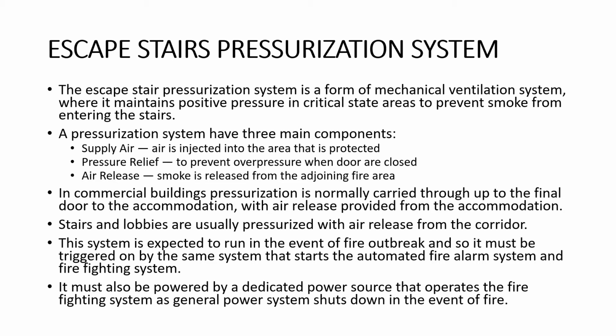For escape stairs pressurization system, the escape stair pressurization system is a form of mechanical ventilation system where it maintains positive pressure in critical stair areas to prevent smoke from entering the stair. A pressurization system has three main components. The first one is supply air, second is pressure relief, and the third one is air release. For supply air, air is injected into the area that is protected. Pressure relief is to prevent overpressure when doors are closed. And the third one, air release, is for smoke to be released from the adjoining fire area.